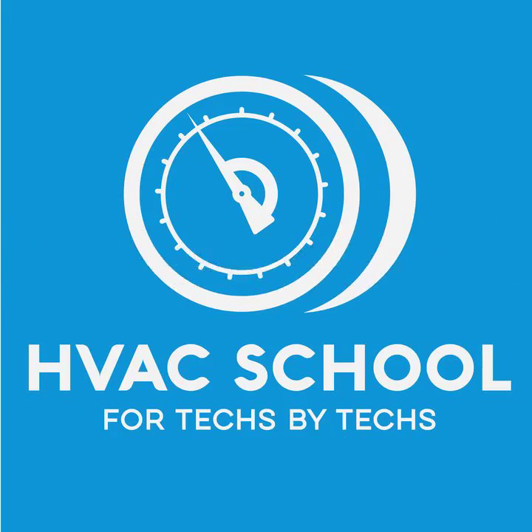There are cases, like Mitsubishi's ductless 6,000 BTU head that matches up with their MXZ system. If you look at the specs on that ductless 6,000 BTU head, at design conditions it removes 0 latent, meaning 0 pints of water, none.